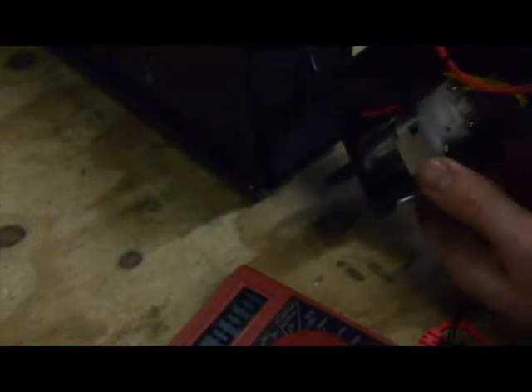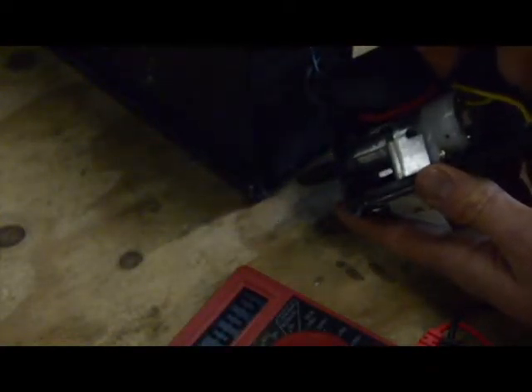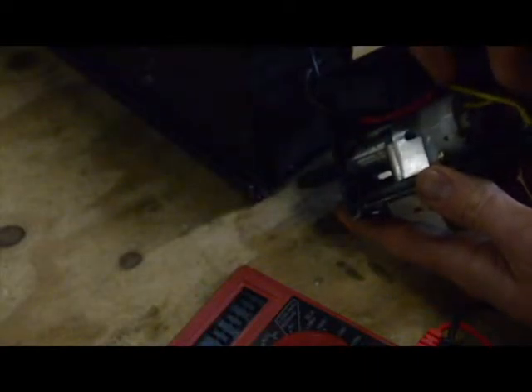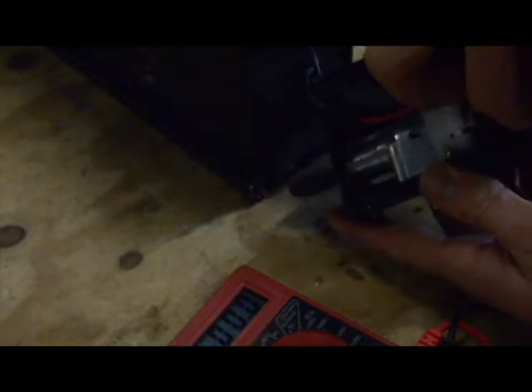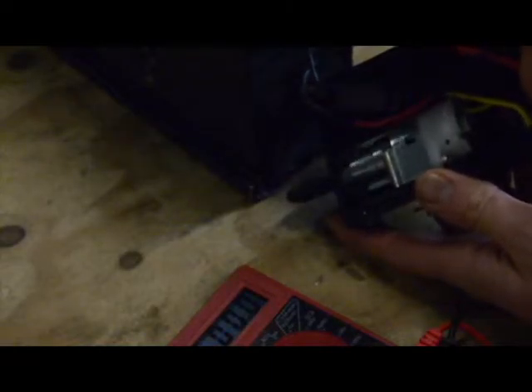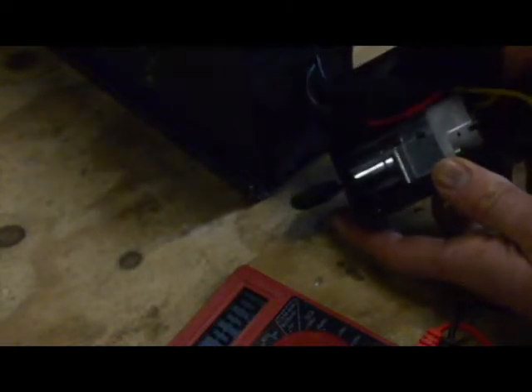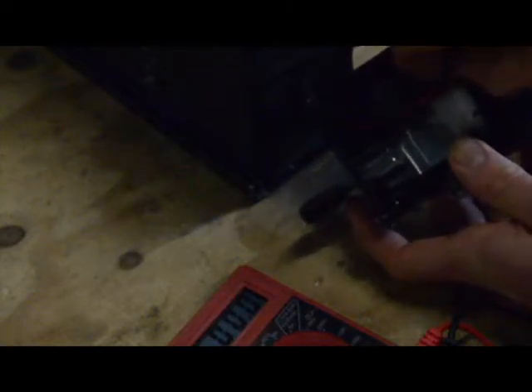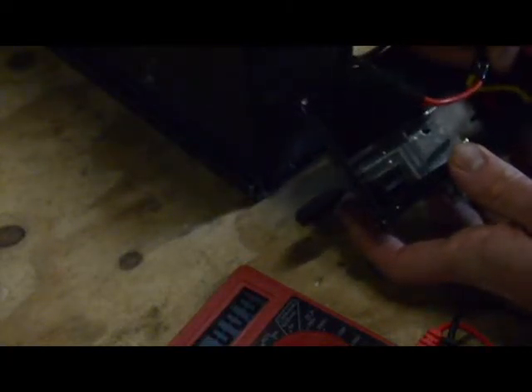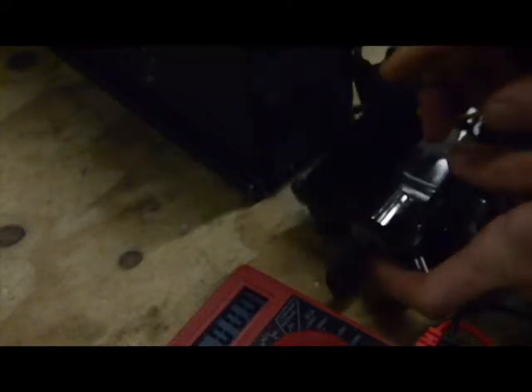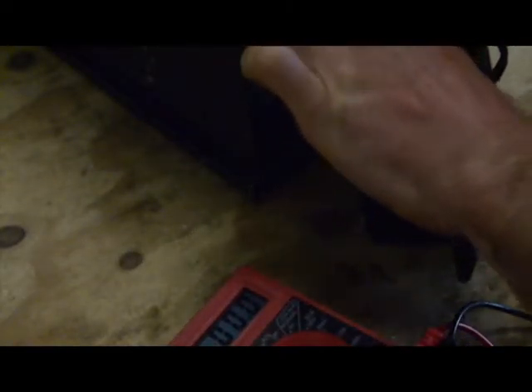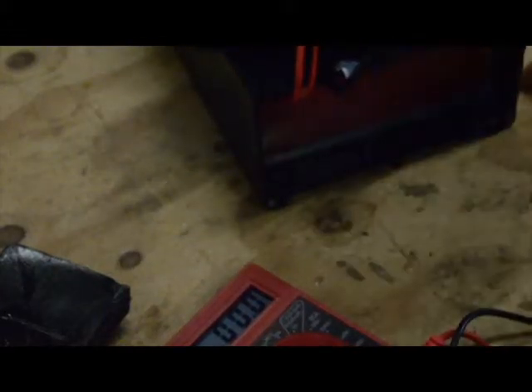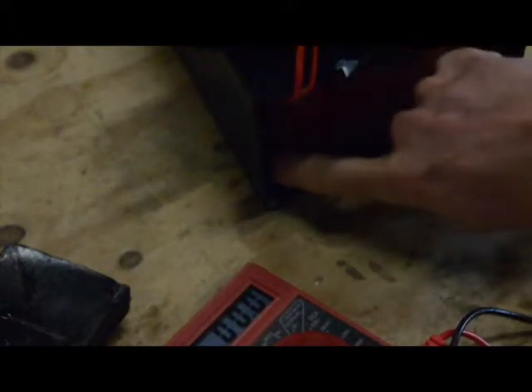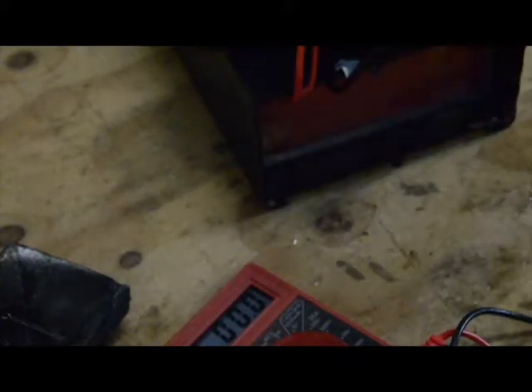And one thing you might want to do is visually inspect, make sure that the red discharge output wire that you were using is not broken down here on the contacts, because we were using that for part of our test. Make sure that the wire coming into the switch is looking all right, looking for stuff that's frayed. And if you're still having trouble, we need to dig in a little deeper, take the foam off, upend our battery carefully, and we want to start opening up the insulator here.